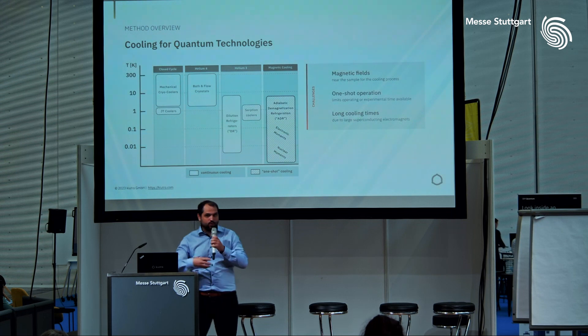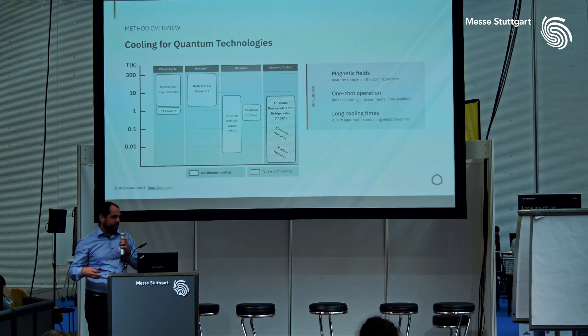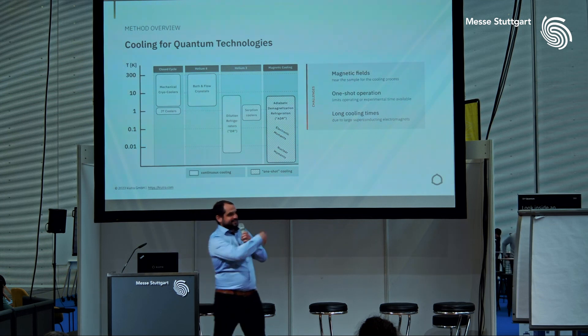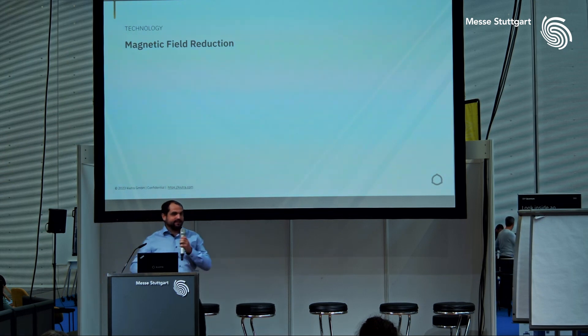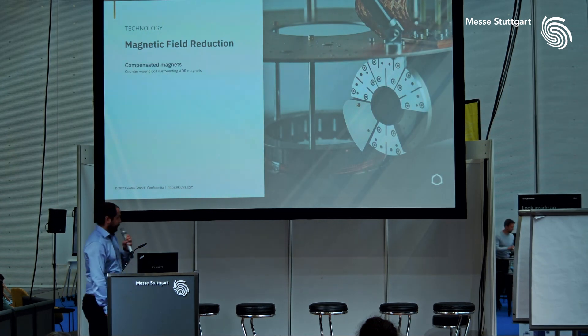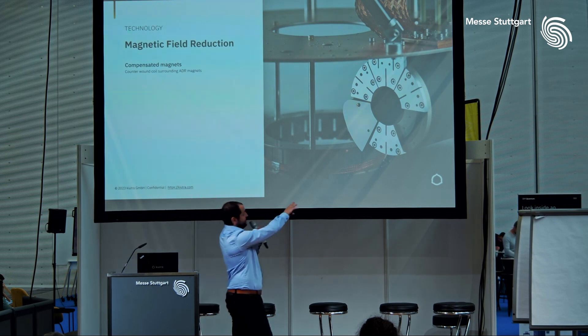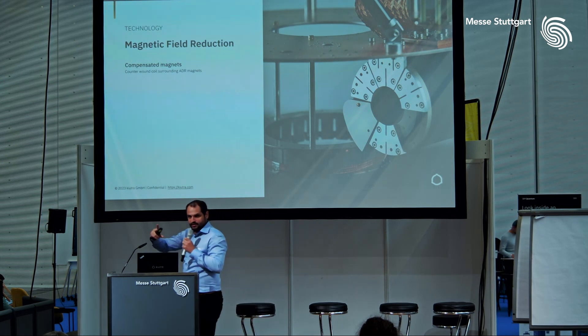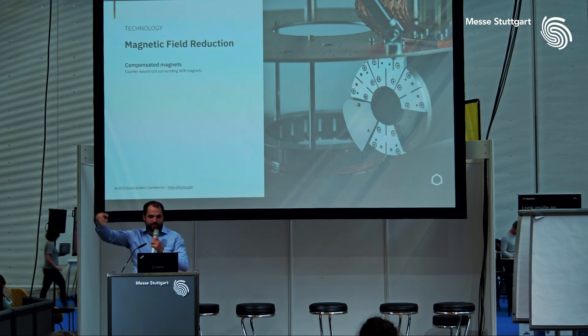Today I'll explain how we have tackled these challenges to harvest the advantages of ADR technology while bypassing its limitations. As mentioned, typical implementations of ADR lead to large stray magnetic fields near the sample, and reduction of these fields is essential to study and operate quantum devices. We use compensated superconducting magnets — you can see one here — with an electromagnet in the middle and a counter-wound electromagnet around it, which actively reduces the magnetic field around the sample.